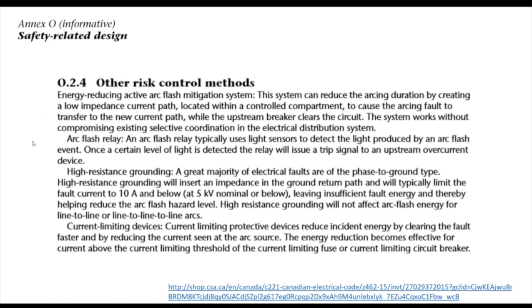A few other items in clause O.2.4, other risk control methods, which lines up nicely with CSA Z1002 and Z462. Energy reducing active arc flash mitigation systems can reduce the arc duration by creating a low impedance current path located within a controlled compartment to cause the arcing fault to transfer to a new current path. In many ways, the engineers in the last 10 years have really come up with some great design concepts and methods to make for a safer workplace and reduce the likelihood of events. Again, arc flash relays, and this is one, of course, we want to touch on today.